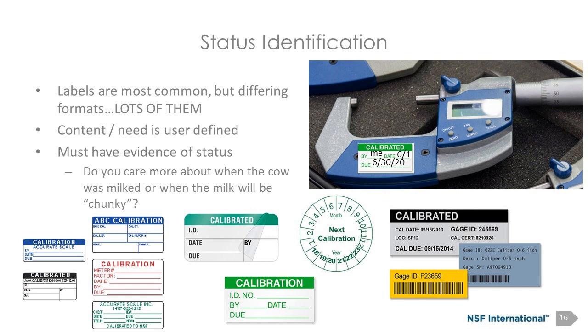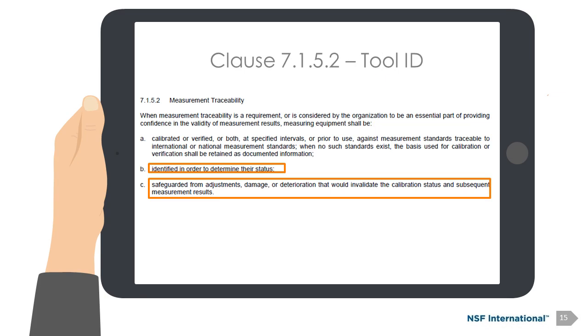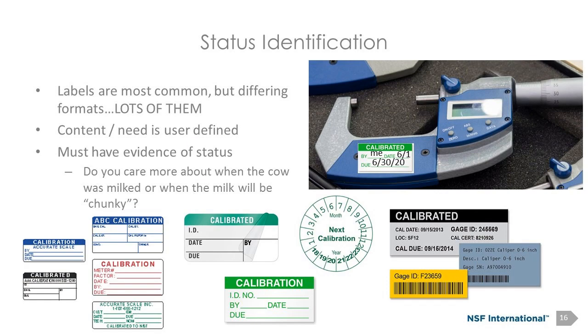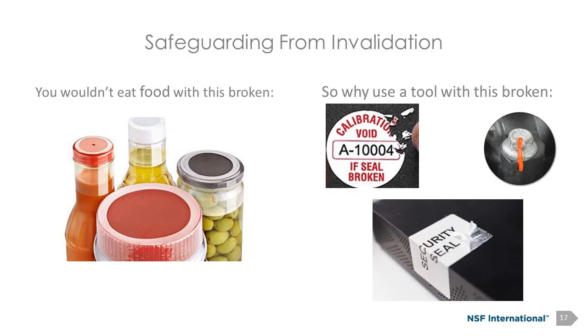Ultimately, that status identifier is going to help us to ensure that the users of those tools know that it's a good tool, that it's conforming to the requirements, that it's capable, etc. It's been blessed as having the possibility of being good. Now, the editorial comment that I threw in here, and for those that I've audited with or audited at, you know that I've said this to you: do we really care about when the milk came out of the cow, or do we care about when it's supposed to go chunky? And pardon the graphic reference here, but the point is, is it necessary for us to have the date that it was done on the label? Is it necessary for us to have the information about who calibrated it on the label? And if we go back to, again, the standard requirement, it simply says identified in order to determine their status. So we're looking for some identifier on the tool that shows us ready or not. Okay.